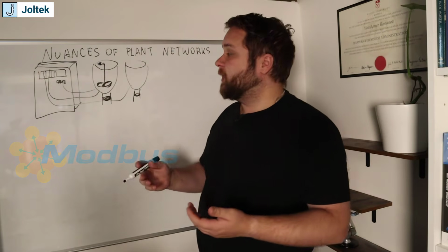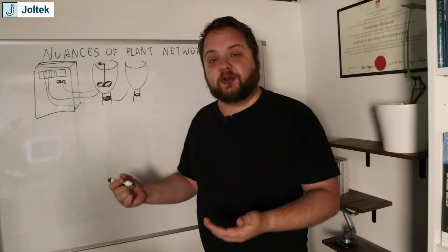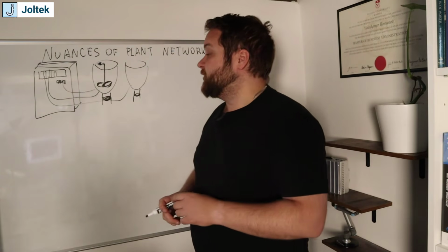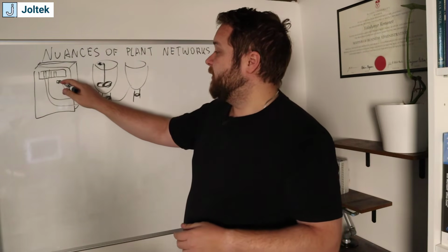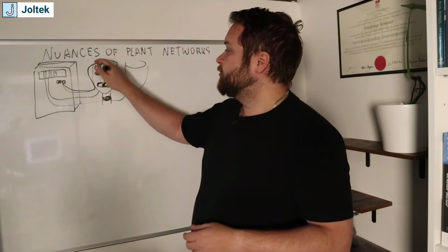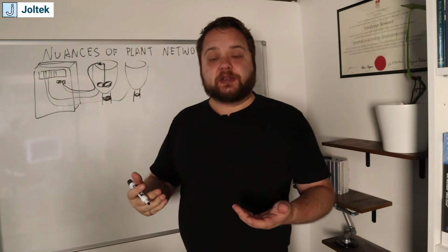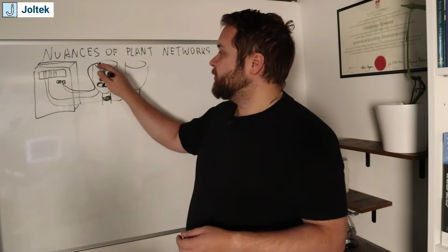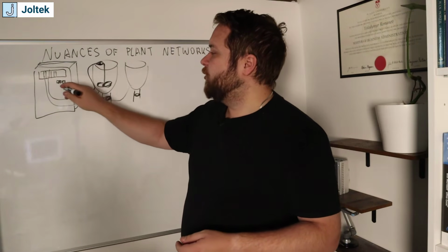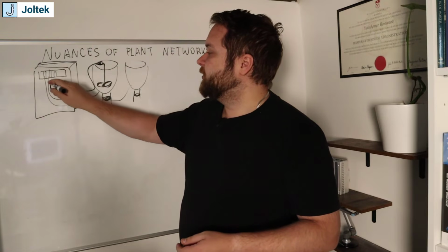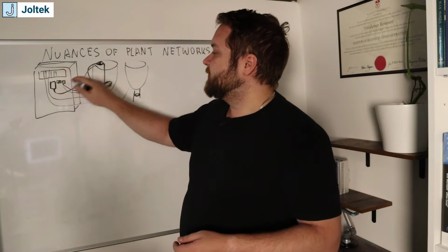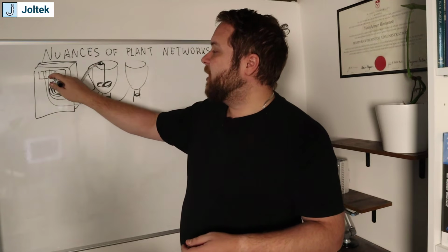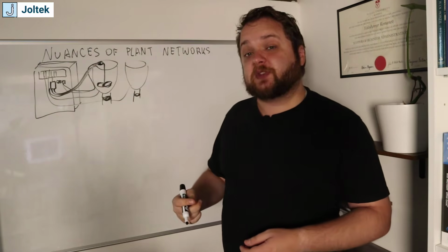the PLC, and it allows you to have more granular control than you would via a digital type of a device. So in this case, if I have a relay that's going to just close the signal to the motor, all I can do is turn on, turn off. If I have Modbus to that specific motor, and let's imagine that now we've added some kind of a drive, right? So this drive is going to be obviously connected via 3 phases to that motor, but now I have Modbus, a connection to that specific drive.